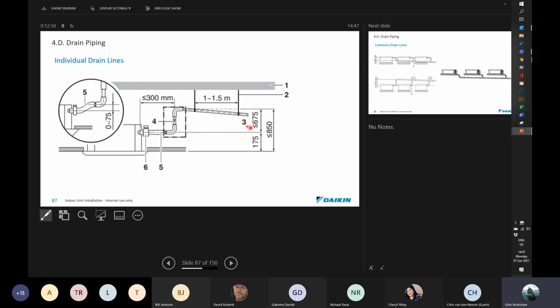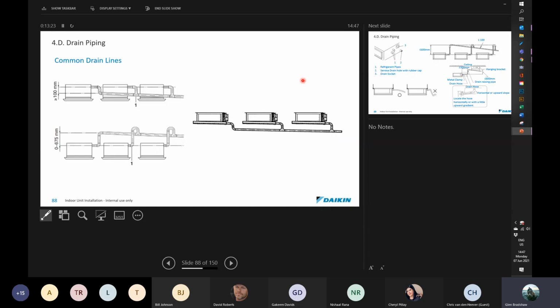Also be aware that the distances can be measured from the ceiling tile on cassettes. Okay, ducted units, because they can sit above the ceiling tiles, their reference would be from the outlet of the unit. So just take note of that when you're looking inside the installation manual for the indoor unit. Where are they referencing this 850 millimeters from? Okay, then using common drains, make sure that the common drain is always sloping down. Okay, if you've got pumps available, you can pump up higher than the unit, making sure, remember, that you don't exceed the maximum lift of the pump. Okay, and that the drain then flows downhill from there. Okay, correctly supported.